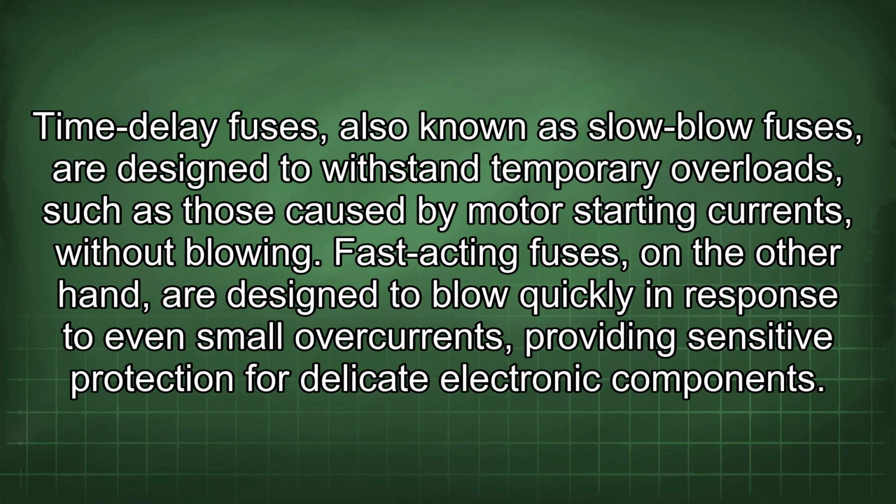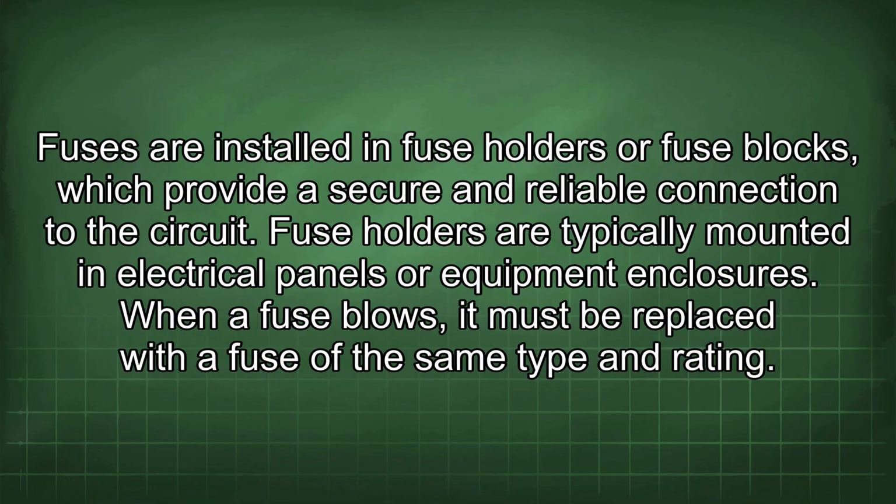Time delay fuses, also known as slow-blow fuses, are designed to withstand temporary overloads, such as those caused by motor starting currents, without blowing. Fast-acting fuses, on the other hand, are designed to blow quickly in response to even small overcurrents, providing sensitive protection for delicate electronic components. Fuses are installed in fuse holders or fuse blocks, which provide a secure and reliable connection to the circuit. Fuse holders are typically mounted in electrical panels or equipment enclosures.